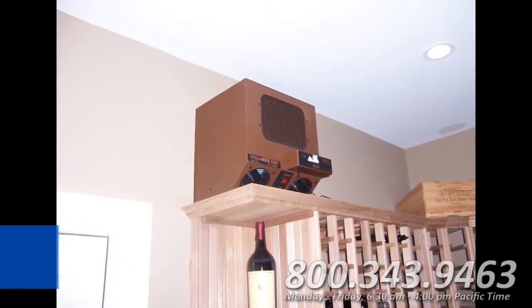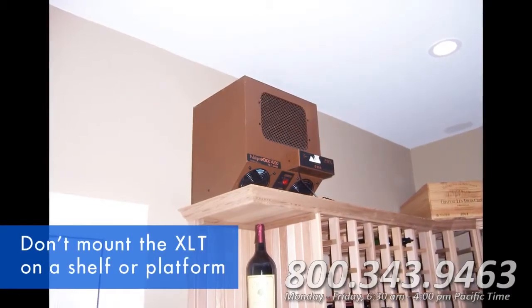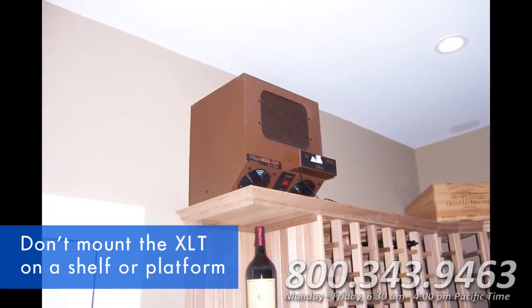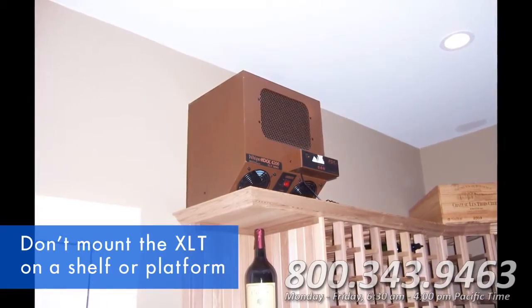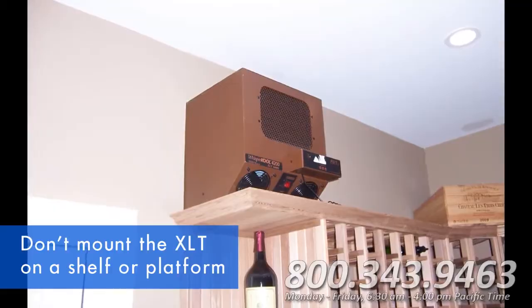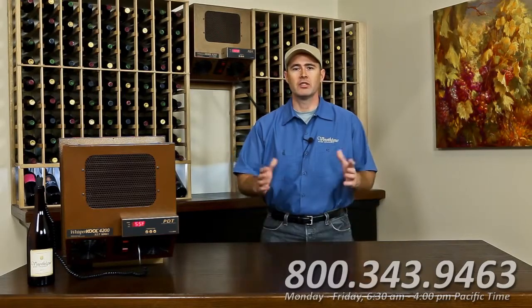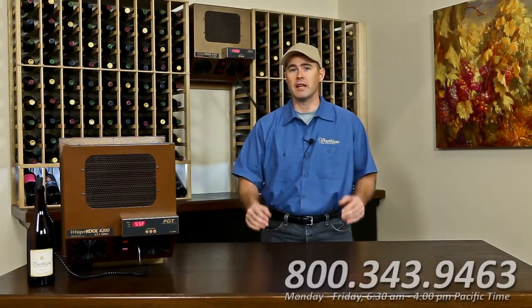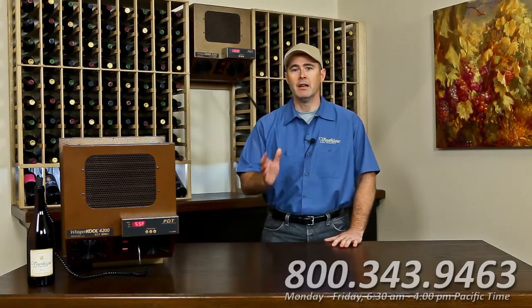Make sure that you do not mount the unit on a shelf due to the 45-degree angle of the fans. If the fans are blocked, ice can form on the evaporator and the grill. If you find ice on your cooling unit, turn it off for 36 hours to allow the ice to melt. Be sure to use towels or a bucket to catch the water as the ice melts. In the meantime, clean the coils and check the fans like we did earlier.